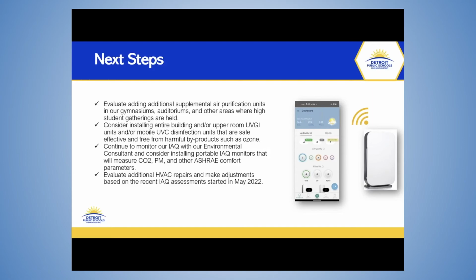Our next steps are to continue to evaluate adding additional supplemental air purification units to our gymnasiums, auditoriums, and other areas where you have high student gatherings. We're also considering installing entire building or upper room UVGI units and mobile UV disinfectant units that are safe and effective and free from harmful byproducts such as ozone. We're also going to continue monitoring our indoor air quality with our environmental consultant. Right now, we're doing this on an annual basis. We're also considering utilizing portable IAQ monitors that will measure CO2, particulate matter, and other ASHRAE comfort parameters.